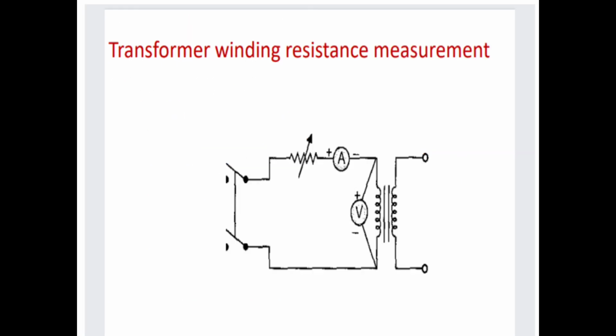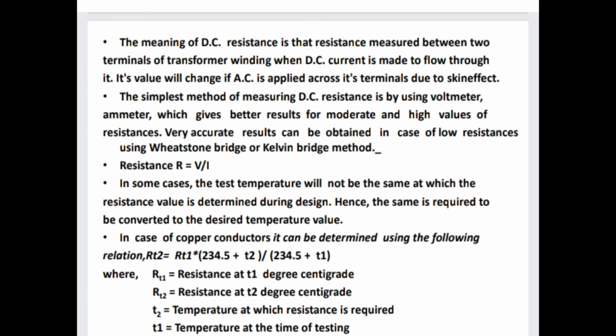So this is the diagram of transformer winding resistance measurement. The measurement of DC resistance is the resistance measured between two terminals of the transformer winding. When DC current is made to flow through it, its value will change if AC is applied across its terminals due to skin effect. The simplest method of measuring DC resistance is by using voltmeter ammeter, which gives better results for moderate and high values of resistance. Very accurate results can be obtained in case of low resistance using Wheatstone bridge or Kelvin's bridge method. Wheatstone bridge and Kelvin's bridge methods are very important.